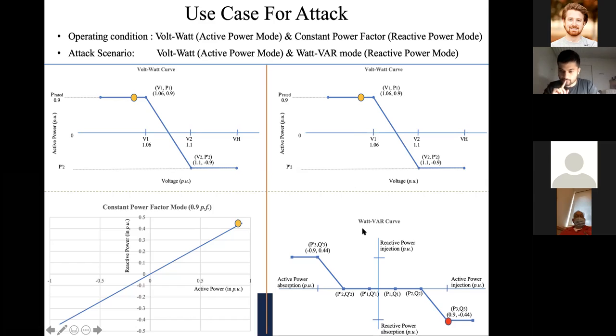But then the thing with the watt-var curve is that it's going to say, okay, I'm going to follow the watt value, and the watt value is 0.9. And if you see this watt-var curve, it goes to negative 0.44, which means it is going to absorb 0.44 pu of reactive power. So you see the problem here. You go from injecting 0.44 pu of reactive power to absorbing 0.44 pu of reactive power. You're just going from generation to absorption because of this malicious mode change. So obviously that's a problem, and it is going to change the voltage and frequency stability and the trajectory of the system, and it's going to change the dynamics, and it's pretty obvious that we can see that, right?